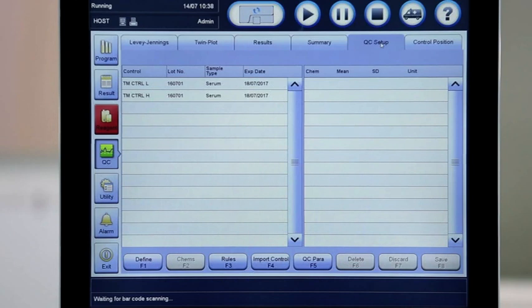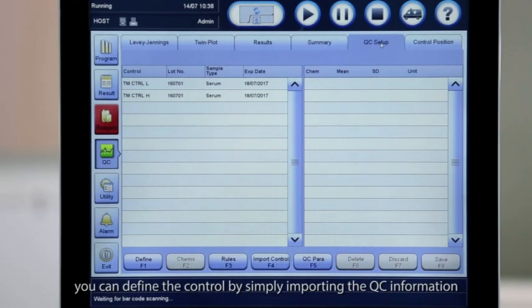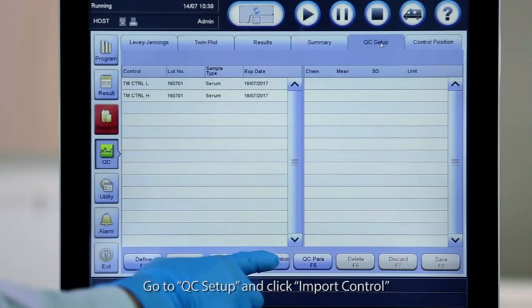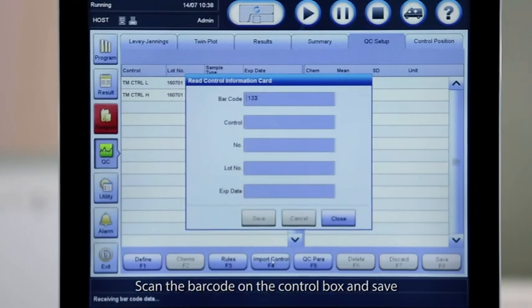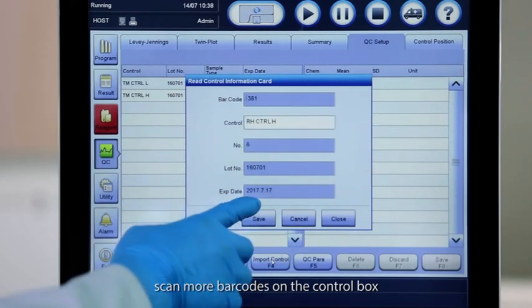If you use Mindray Internal Control, you can define the control by simply importing the QC information. Go to QC Setup and click Import Control. Scan the barcode on the control box and save. To define more controls, scan more barcodes on the control box.